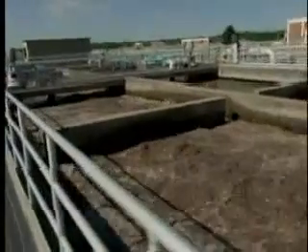And at this point it should be mostly all bacteria, because the bacteria should have eaten or have assimilated most of the waste in the wastewater. So when the bacteria do settle in this tank, we pump them back to the head of the aeration tank because they're like hungry again and ready for more waste from the primary treatment process.